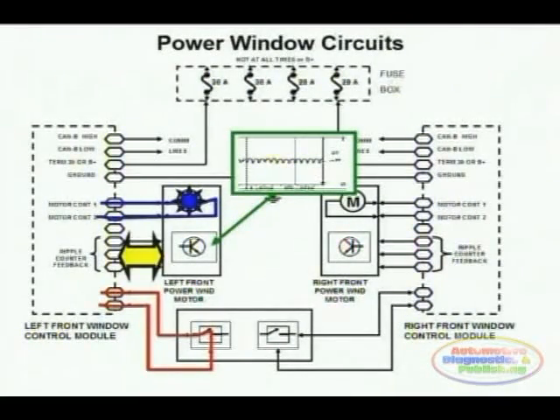Rather than using a different method, for example, in the older systems, you would use some kind of thermal relay within the switch itself, which is a mechanical component. As soon as the module sees that no more ripple is being detected, the motor is not turning, it would immediately shut off the motor.